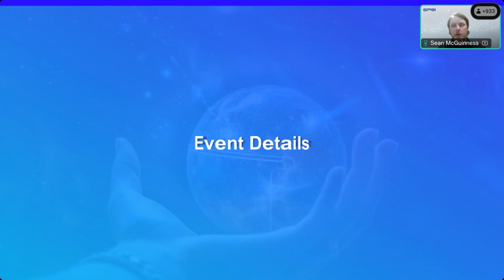So we're now going to go into the actual main event itself, and to reiterate what Daniel mentioned earlier, we're presenting the data that we have, and it's extremely important not to just take available data and make conclusions from that. We have to consider that there's data we would like to see, and you need a full data set to be able to make conclusions about what actually happened. We don't have voltage profiles across the Spanish grid. We don't know what generators tripped in what sequence. There's a lot of unknowns. So we want to emphasize that we're displaying the data that we've found, but we don't have a complete data set, so we can't make a definitive conclusion on exactly what happened.